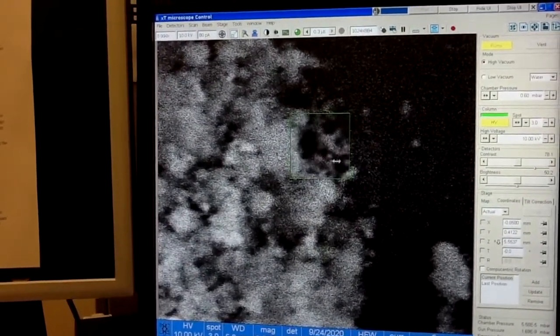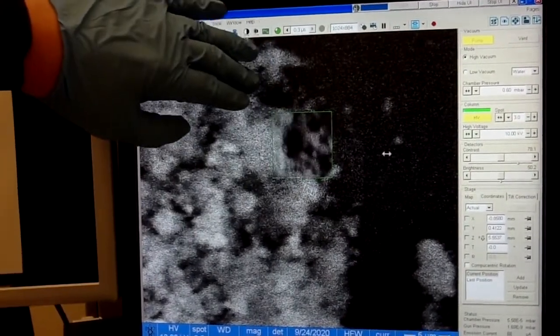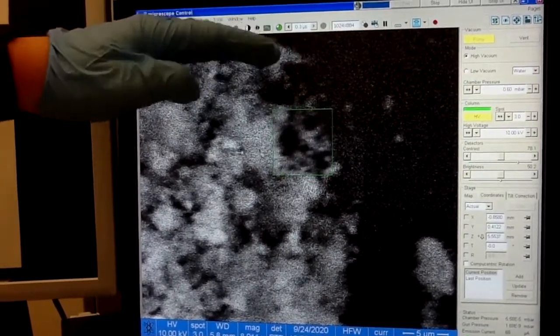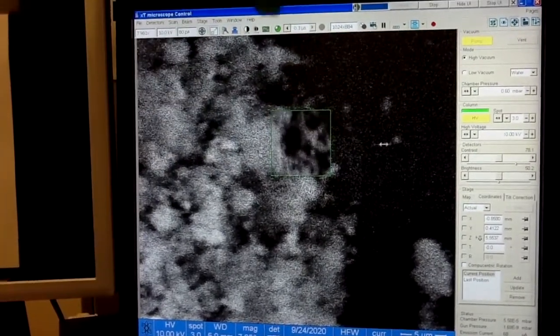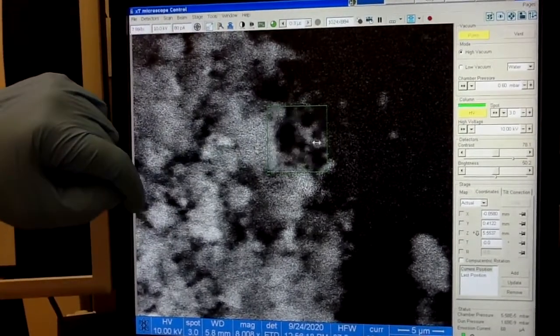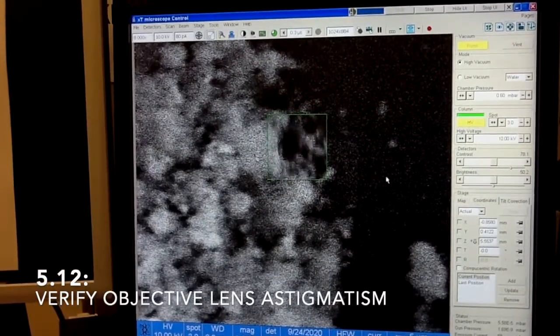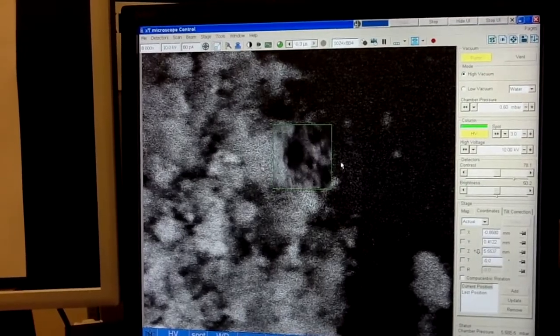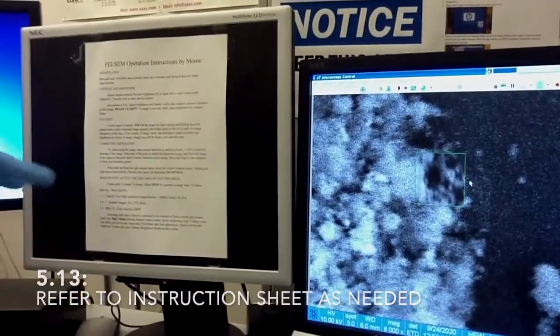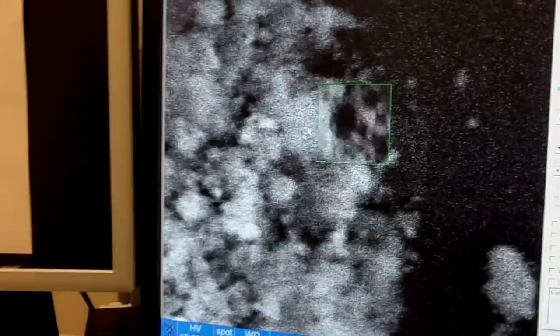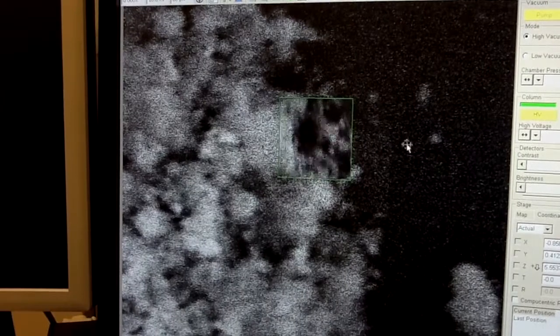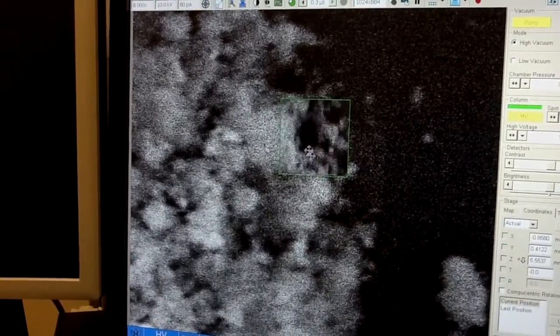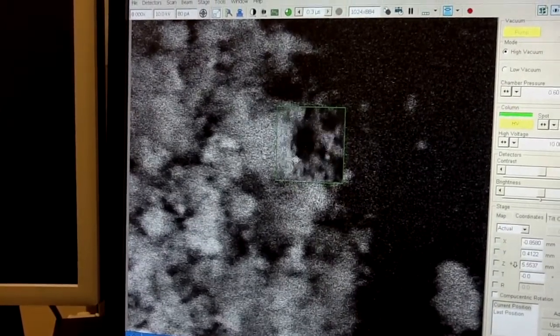So, if you focus, you will see that there starts to be elongation in this direction, if you move the mouse in one direction. And elongation in this direction, when you move the mouse on this side. So, you see there is elongation in this side or in this direction, which is a clear indication that we have objective lens astigmatism, which we need to correct. Now, to correct the astigmatism, there is an instruction here on this note. You can read it if you forget, but hold the shift button and then press the right button on your mouse and then move again to get the best focus. And you move right to left and also up, down and up.